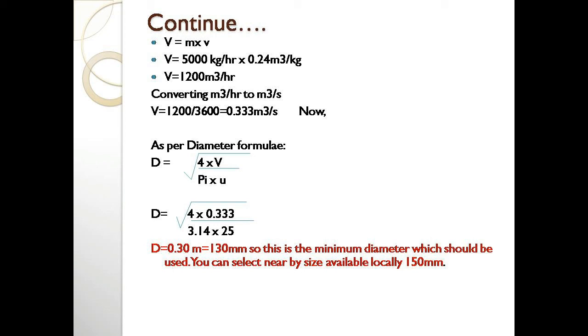Applying the diameter formula: D = √(4V / πU), and substituting all values, we get D = 0.130 meters, which is 130 mm. Therefore, for a requirement of 5000 kg per hour of steam, the minimum pipe size needed is 130 mm.